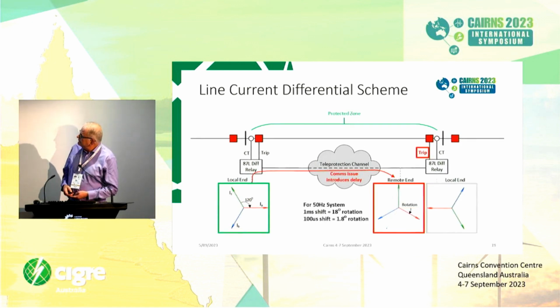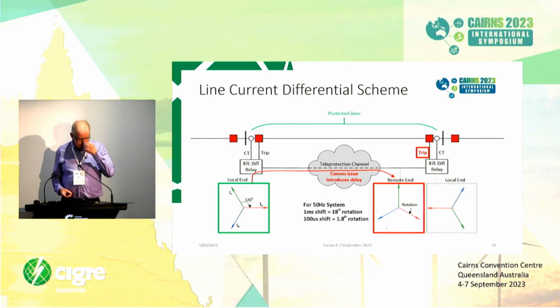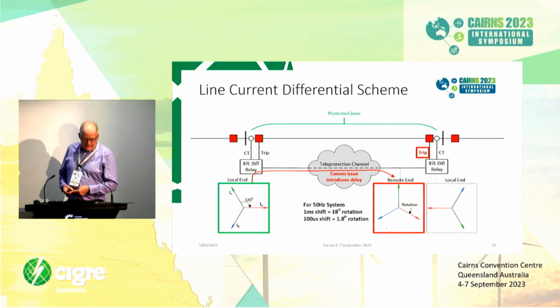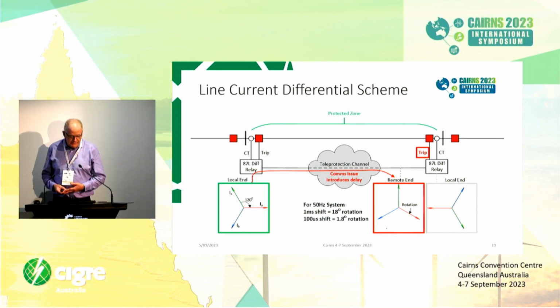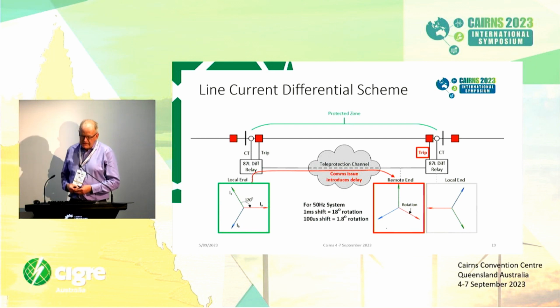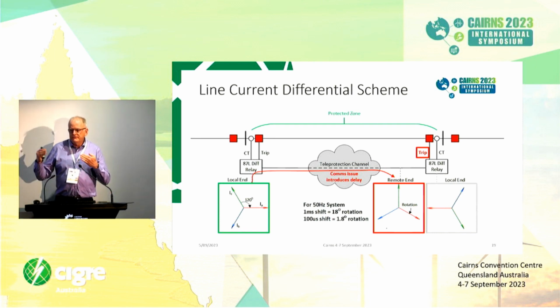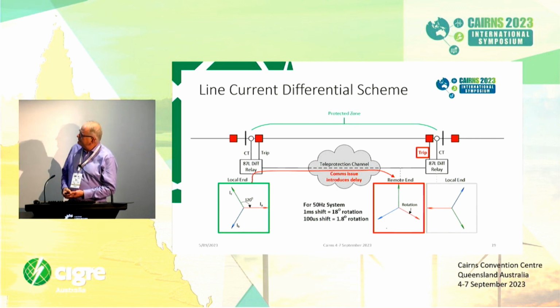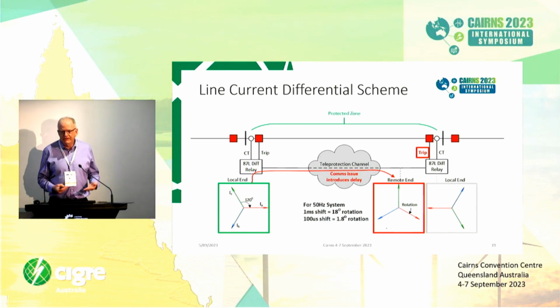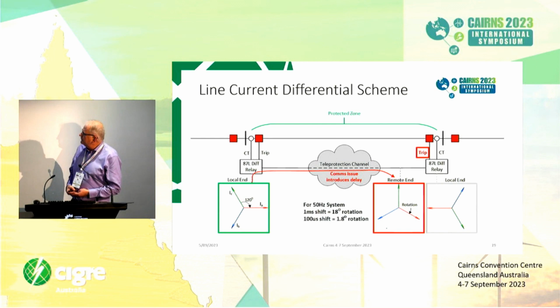But what happens if we get some sort of a communications issue that could cause some delay variance? That can result in a rotation of the current vectors at the receiving end, the remote end. Once again, the remote end relay will try to sum the current vectors. This time though, there's an angular difference from that rotation caused by the communications issue. That will mean you'll get some spill current being detected, some difference in the two current vectors, which could trick the relay into thinking that there's a fault on the line and could cause the relay to pick up and trip the line, which is not good, obviously. So we've tripped for a problem with our communications network, which we obviously want to try and prevent.